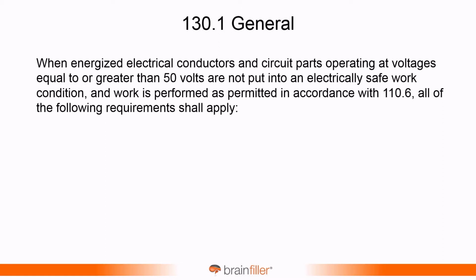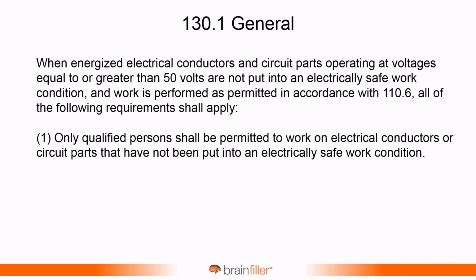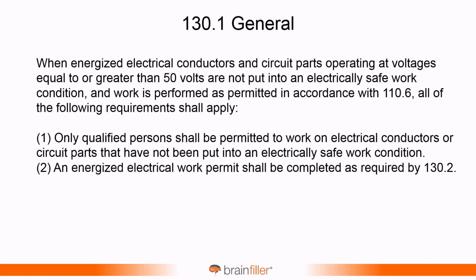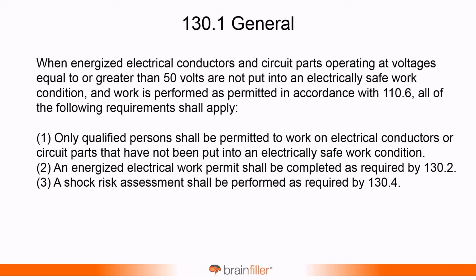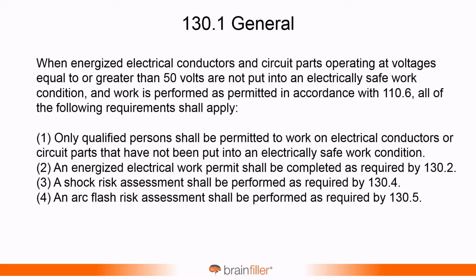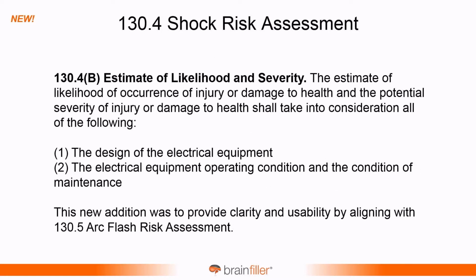With this one, when energized electrical conductors and circuit parts operating at voltages equal to or greater than 50 volts are not put into an electrically safe work condition, and work is performed as permitted in accordance with 110.6, that used to be in 130, all of the following apply. Only qualified persons are permitted to work on the electrical conductors. An energized electrical work permit shall be completed, and the shock risk assessment performed, and the arc flash risk assessment performed. And so this is a lot of the same concepts, although some of this was reworded as part of the reorganization that has occurred.